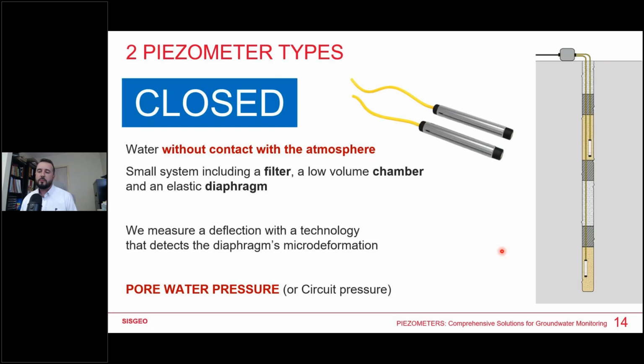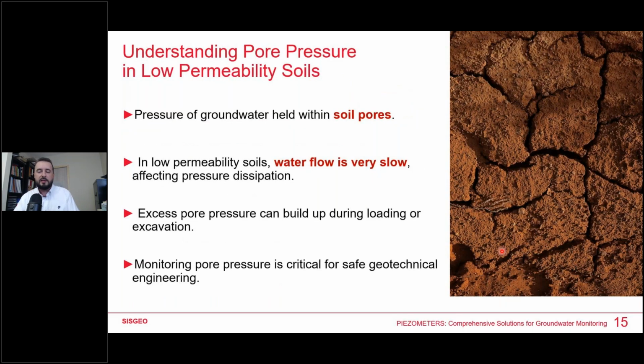In the closed type, on the contrary, the water is not in contact with the atmosphere, it's sealed. So it's a small system using a filter, a low volume chamber, and very important, an elastic diaphragm. I will speak about it a bit later. We measure basically the deflection of this diaphragm, and we use a technology that detects the micro deformation of this diaphragm. For this, the main application is pore water pressure monitoring. We can also use this kind of closed system to monitor circuit pressure. It's the same principle.